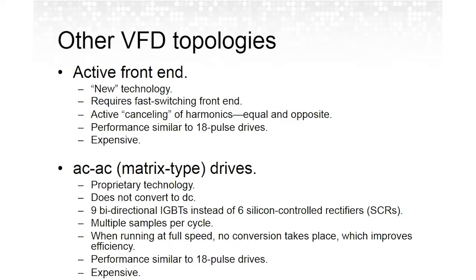The other emerging technology is the AC to AC drive, or matrix type drive. Basically, we're eliminating that double conversion step, AC to DC to AC, and going straight from AC to AC. What we have is a series of 9 switches arranged so that any single one of the 3 input phases can be connected to any of the 3 output phases. And it's also bidirectional. So we can also push power back out onto the source if we had to in regenerative applications where we're trying to slow something down or reverse it.